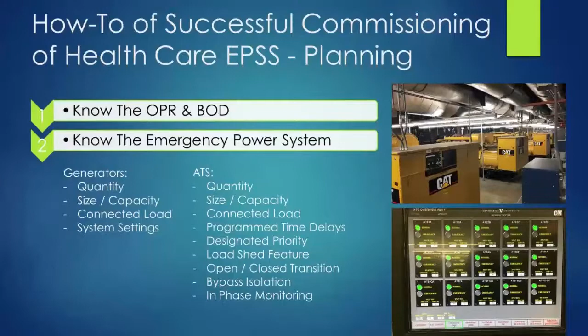Your ATSs — what's the quantity, the size, the capacity? What's the connected load, the program time delays, designated priorities, load shed features? Is it open or closed transition, bypass isolation? Does it have in-phase monitoring? All of this, again, you need to gather in order to know how you should test it and how the system is actually going to operate.